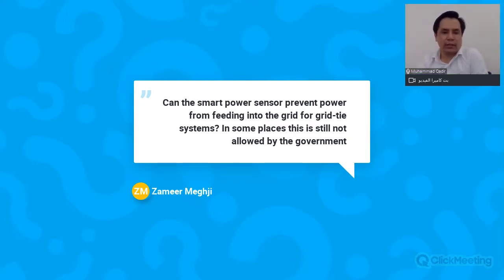The next question: can the smart power sensor prevent power from feeding into the grid from grid-tie systems? In some places, this is still not allowed by the government. The previous question was similar to this, and the answer is yes, you can do zero export. Share with us your project scenario, and we will advise you how you can achieve this. Either you can connect a power meter directly to the inverter model that you're using, or you can have a smart logger and connect the power meter to that and do the zero export function. So it depends on what inverter model you're using and what your project scenario is. We can advise you, and the answer is yes.